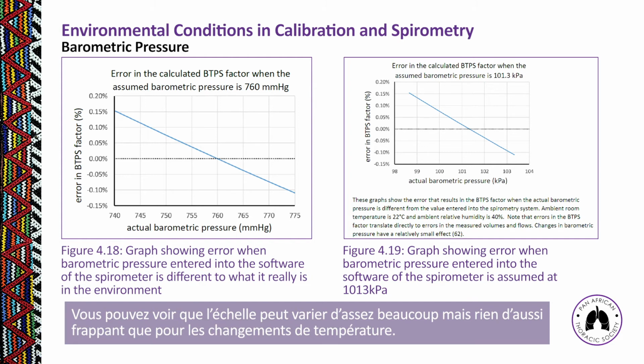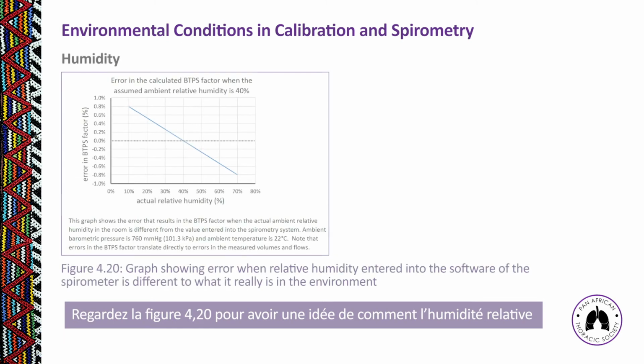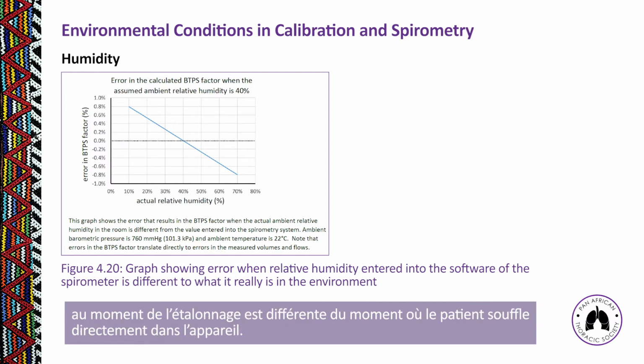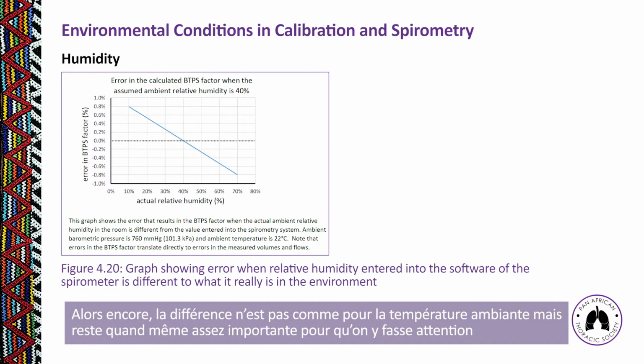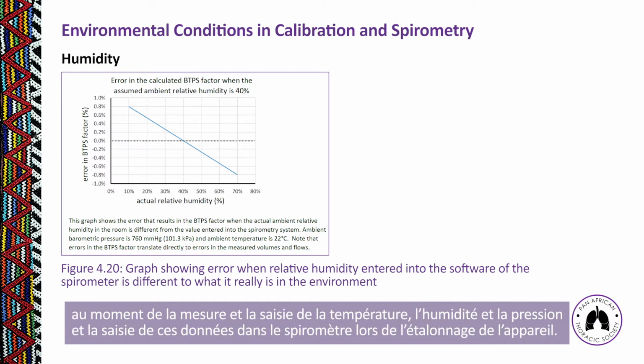Look at figure 4.20 to get a sense of how the relative humidity at the time of calibration differs when a patient blows into the machine itself. So again, also not as severe as the differences in ambient temperature, but nevertheless significant enough for us to pay attention to measuring and entering our temperature, our humidity, and our pressure when we are calibrating a machine.